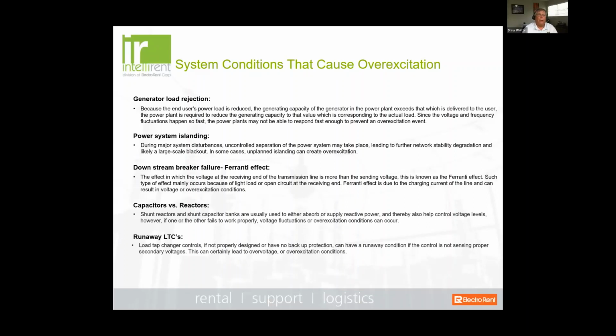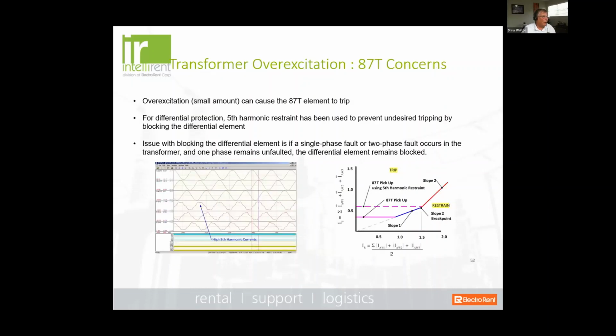So is it important in some situations to enable volts per hertz protection on a non-GSU high voltage transformer? I would say yes, it is. It certainly will do no harm. And given that you could have any of these system conditions, that is important to know.